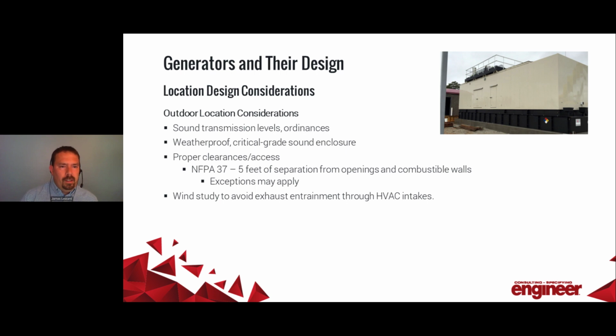And then in the instance of an outdoor located generator, you'll find sometimes you'll have sound transmission ordinances where, and I know in the state of Illinois, they have very strict requirements about the level of mechanical noise that you can generate at the property line. And so you have to be very cognizant of the ordinances and how far this generator has to be set inbound to the property line to avoid having a certain decibel threshold at that line.